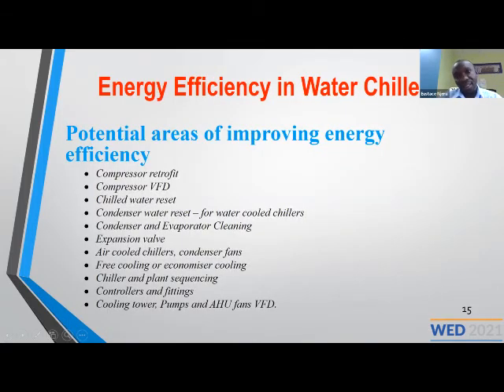So, potential areas of improving energy efficiency in a compressor, in a water chiller. One of them is to do a compressor retrofit. You have to check your water chilling system and the cooling system, and check the amount of load. If the amount of load is not very high, use a small chiller. But if it's very high, you need to use a different type of compressor, probably the centrifugal compressor or the screw compressor. Reciprocating compressors for small chillers are more convenient than, say, a centrifugal compressor.